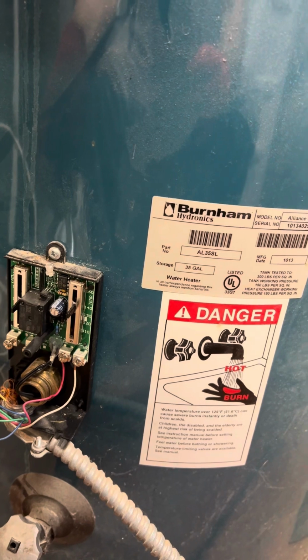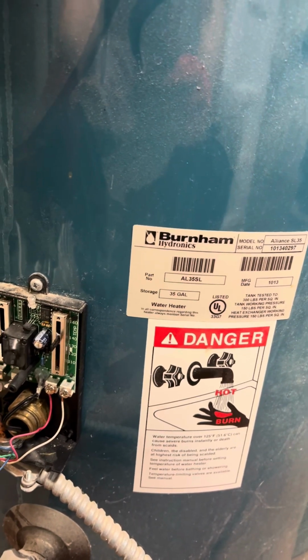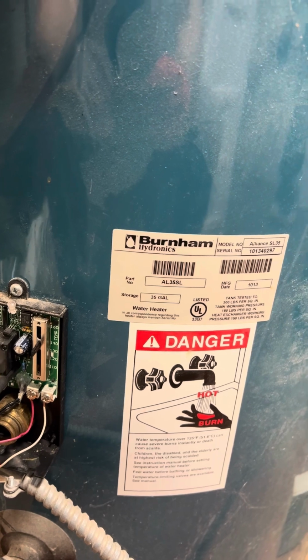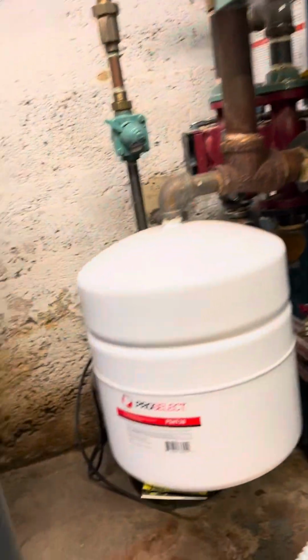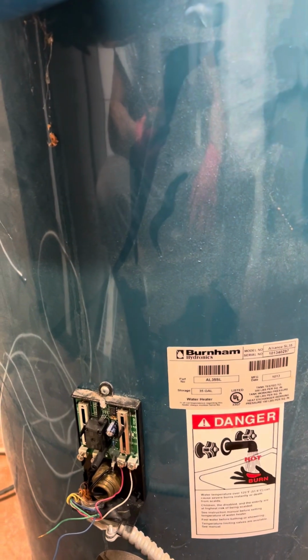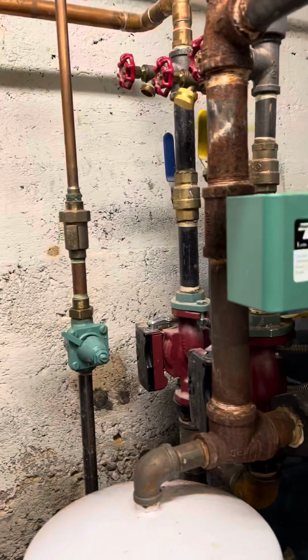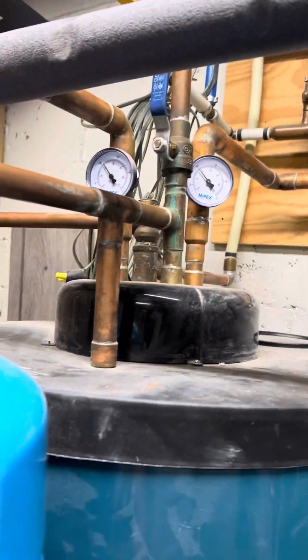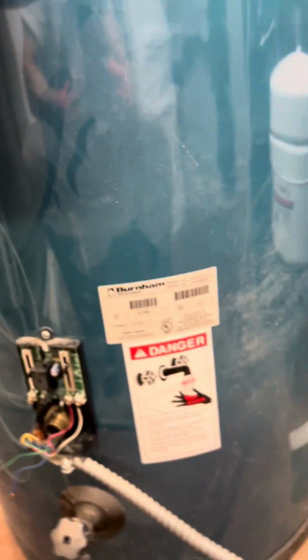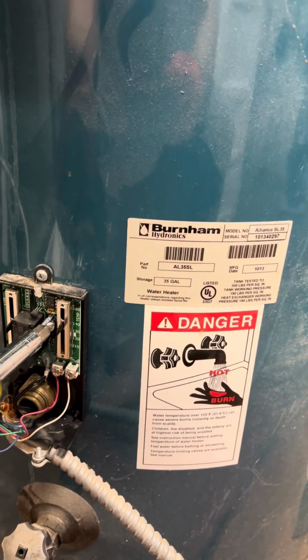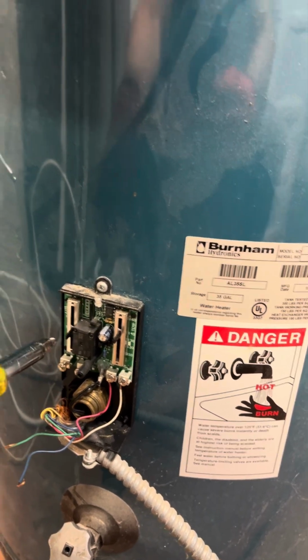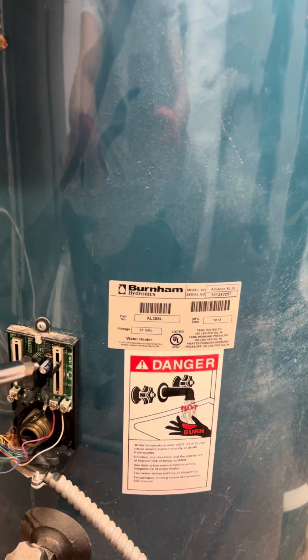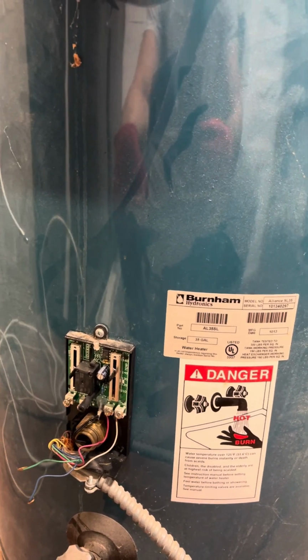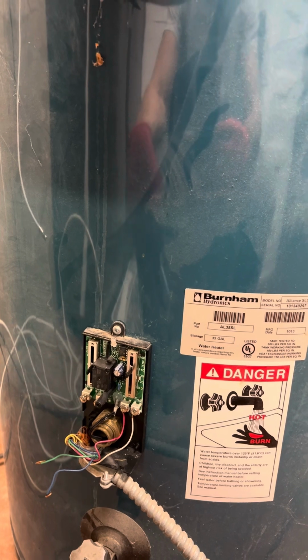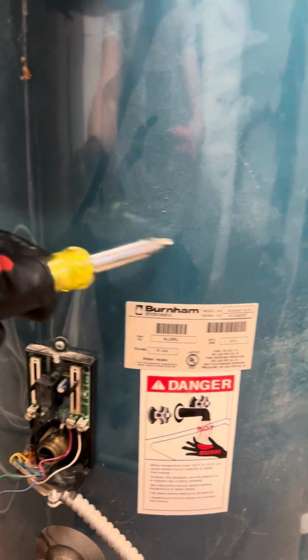So if it's coming through, say on the green, so the power just stops right here. When this Aquastat closes, it'll go from here to here, back to the blue, all the way back, up, down, in, and right into that blue. And the boiler will know that it needs hot water. That will key the circulator for this one zone, okay? And then you'll have hot water. Once it gets up to whatever you set it at, which is around like 130 here with probably a 10-degree differential, so it shuts off at 130, turns back on around 100, or if it's 10 degrees, it'll be 120, and you'll have hot water in this tank this whole time.